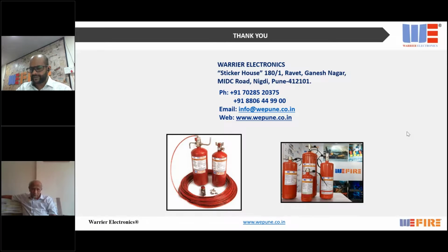Your voice is not audible, can you repeat the question? The pressure switch is there in our fire extinguisher system, right? Yes, pressure switch is there, but it is not used for detection. Our pressure switch is only used to connect to your machine, to shut off the machine, the fume extractor, or the auto door closure. So our pressure switch comes into the picture only when the system has been activated. The primary detection happens through the detection tube. Is that what your question was?